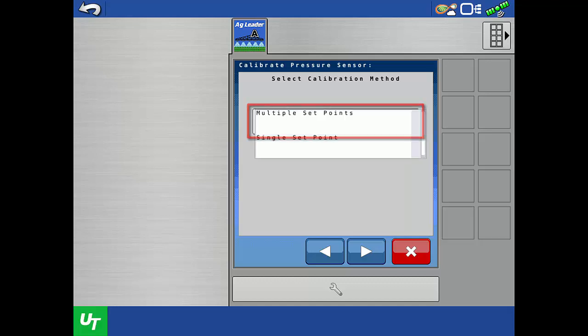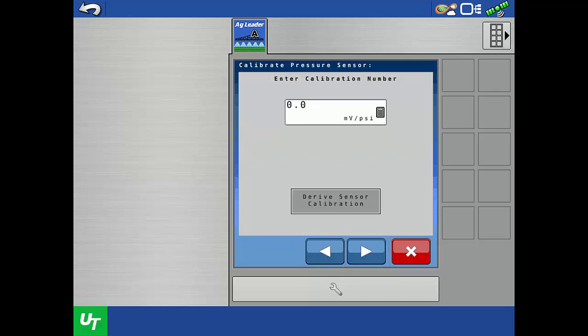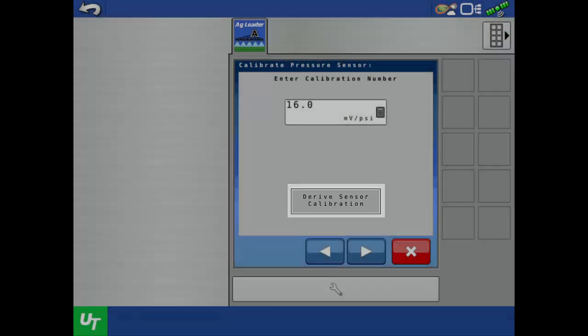Tap the dropdown and select Single Set Point, then tap the next arrow. On this screen, we will need to enter the sensor calibration number. Ag Leader sensors use a calibration value of 16 millivolts per psi, so we will enter 16 here. If you don't know the calibration number, it can be calculated from other known values using the Derive Sensor Calibration Wizard.